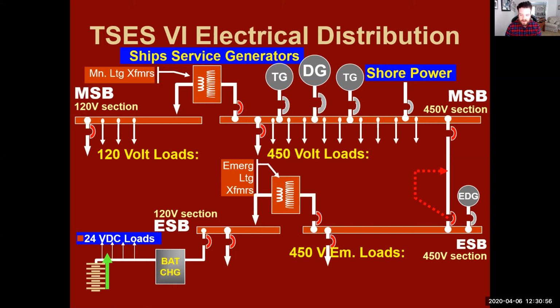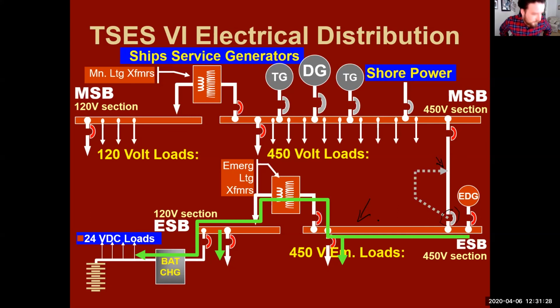And this is what we have: a sensing line. This breaker right here is sensing the power coming from your main switchboard. When there is no power coming from your main switchboard, this breaker will pop open, and thus your emergency generator will start, and it will feed only your emergency generator load. Because these are smaller generators, they're not made to handle the entire ship's load. You have very specific emergency loads, and that's it.